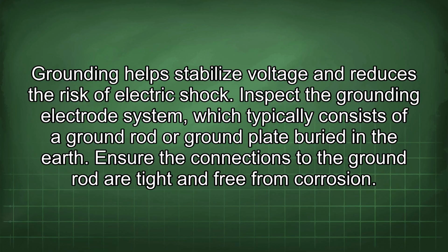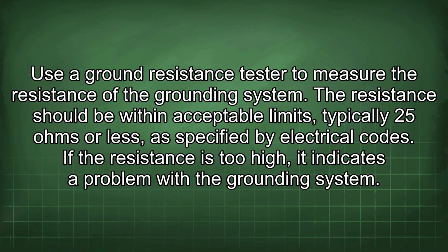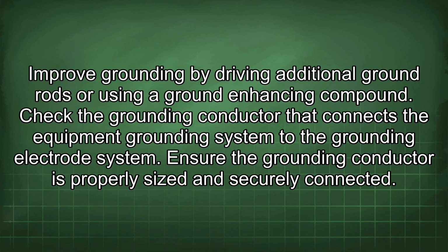Inspect the grounding electrode system, which typically consists of a ground rod or ground plate buried in the earth. Ensure the connections to the ground rod are tight and free from corrosion. Use a ground resistance tester to measure the resistance of the grounding system. The resistance should be within acceptable limits, typically 25 ohms or less, as specified by electrical codes. If the resistance is too high, it indicates a problem with the grounding system. Improve grounding by driving additional ground rods or using a ground-enhancing compound.